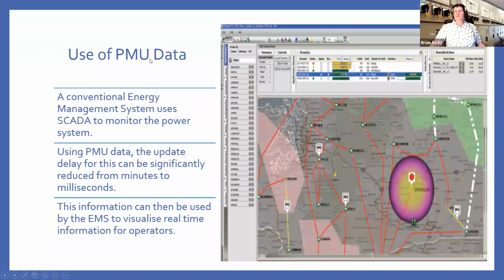PMUs, phasor measurement units, have been widely deployed in some parts of the world. National Grid has deployed some for trials, but it's not across most of the network at the moment. And they are widely being used now in these system stability systems to then feed into your energy management systems, and they can give you visualization of hotspots on your network in close to real time. Typically a phasor measurement unit will be giving you 50 measurements per second. So even so, that's a lot faster than the several minutes you would have on your SCADA systems.